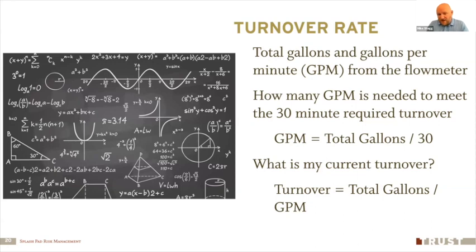Okay, that is state code, a state requirement that we've got to do. So we've got to make sure that you know what your turnover rate is for your specific facility. Okay, it's very important that we know that, so that we make sure that all of the water is being treated in a way that we need it to be treated, and that complies with the state code of 30 minutes that it has to turn over.